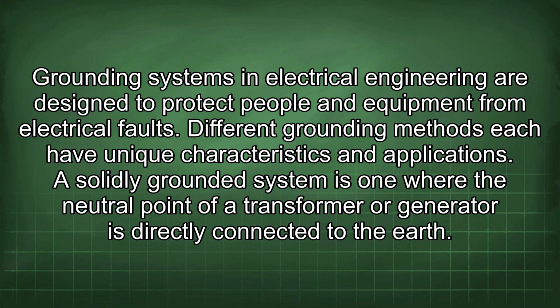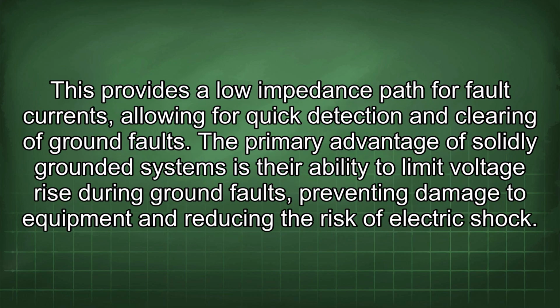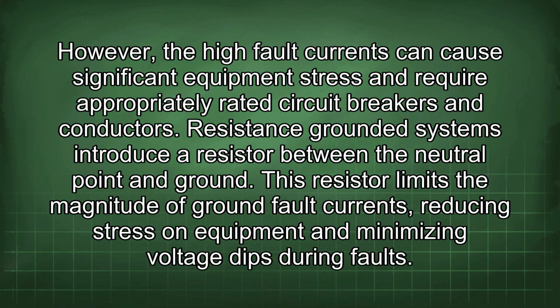A solidly grounded system is one where the neutral point of a transformer or generator is directly connected to the earth. This provides a low impedance path for fault currents, allowing for quick detection and clearing of ground faults. The primary advantage of solidly grounded systems is their ability to limit voltage rise during ground faults, preventing damage to equipment and reducing the risk of electric shock. However, the high fault currents can cause significant equipment stress and require appropriately rated circuit breakers and conductors.